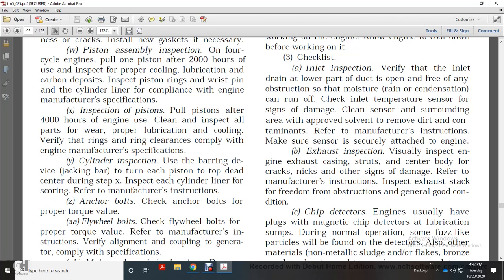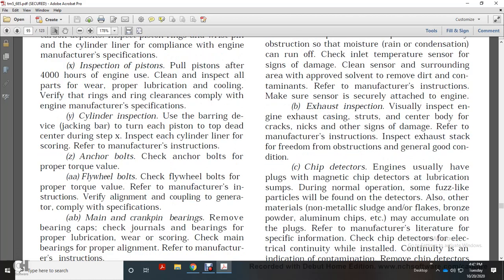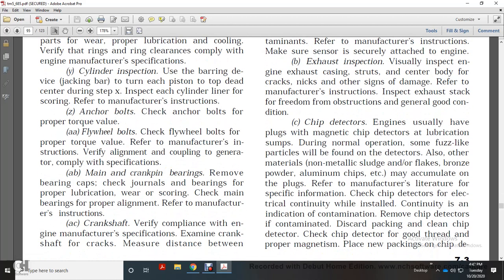Z. Anchor bolts: check anchor bolts for proper torque value. AA. Flywheel bolts: refer to the torque value and the manufacturer's instruction, verify alignment, and couple to the generator in compliance with specification. AB. Main and crank pin bearings: remove the bearing cap of the crank, check journals and bearings for proper lubrication, wear, and scoring, and check the main bearings for proper alignment, referring to the manufacturer's instruction.